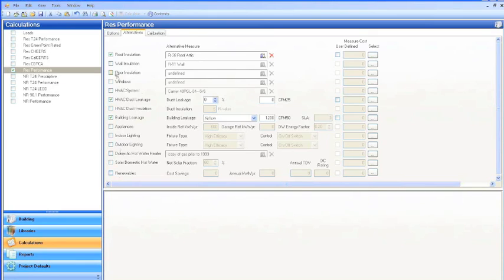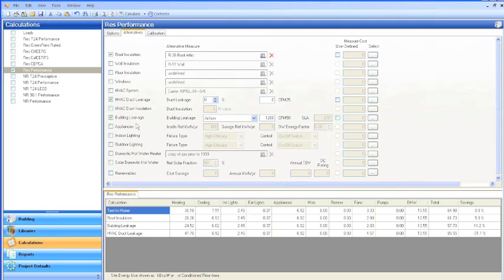If you have more elements in the model, it'll take longer to run because it looks at each one of them in turn. But it's looking at the interactive effects, which means the effect of doing them together. Because as soon as you, for example, insulate the roof, now the air conditioner doesn't need to run as much, because the house is going to stay cooler longer, or stay warmer in the winter longer. And so you're going to be affecting the effectiveness of all these other measures in turn.